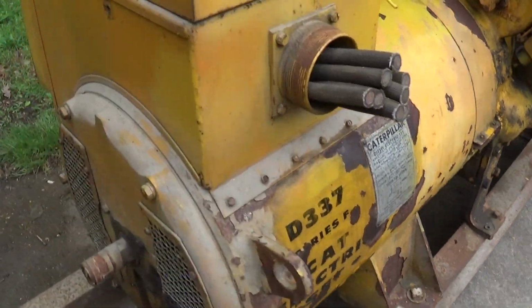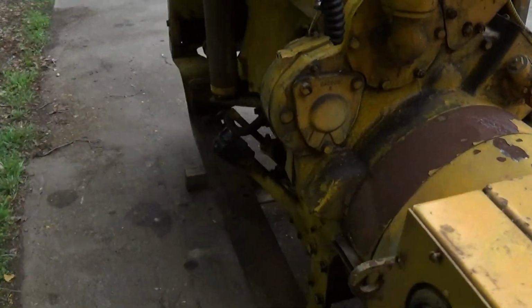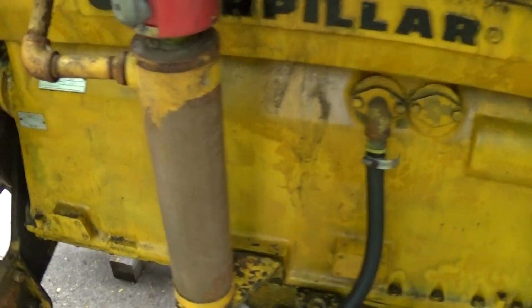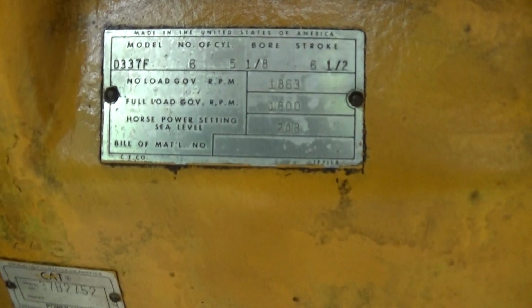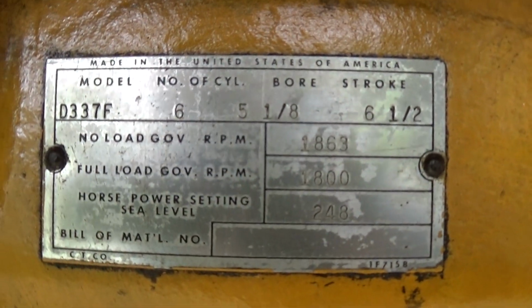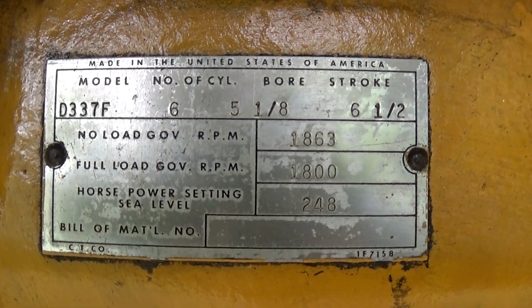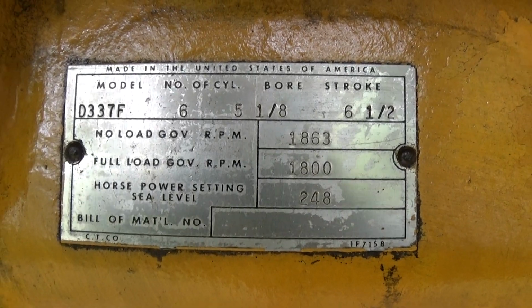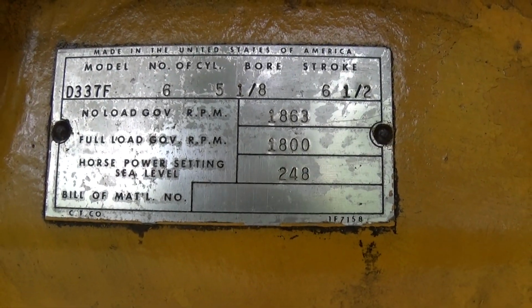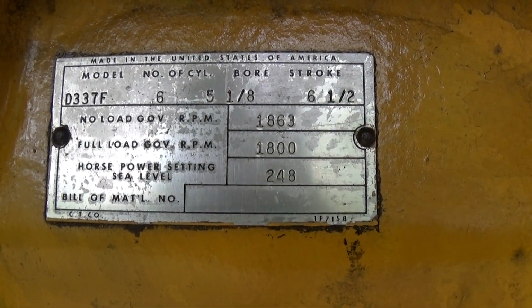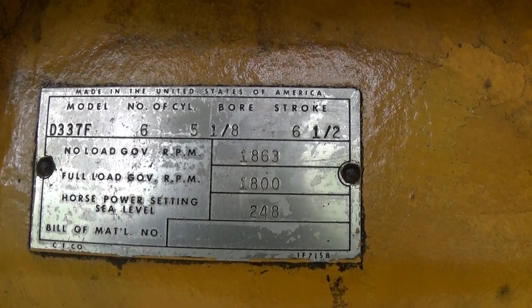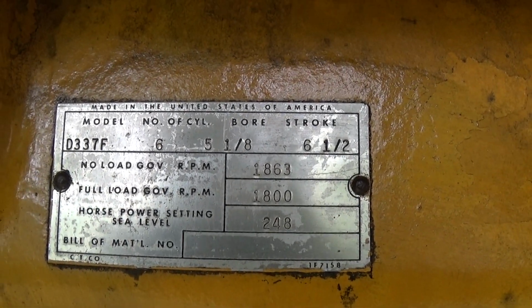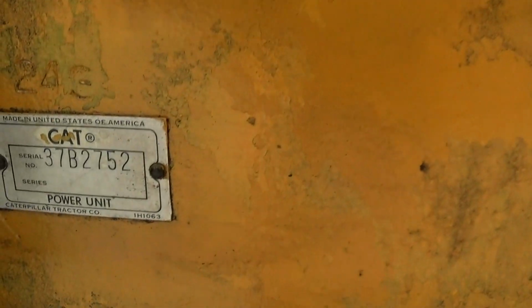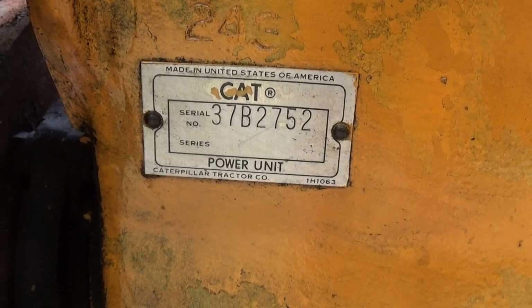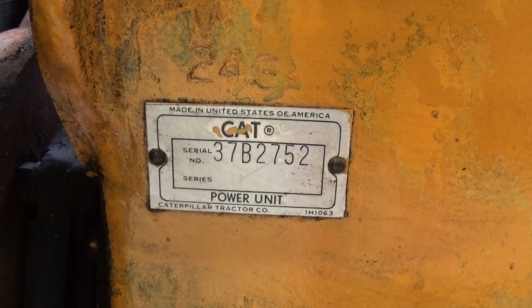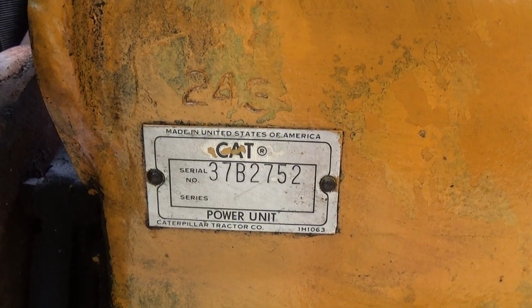From here, let's move on to the engine data plate. We've got a D337F, 5 1/8 inch bore, 6.5 stroke. Loaded RPM is 1800 of course, for 60 Hertz on a 4-pole generator, and no load at 1863. There's our serial number. If anybody can give me a specific build date, I would appreciate it.